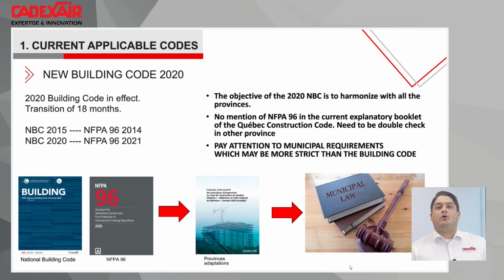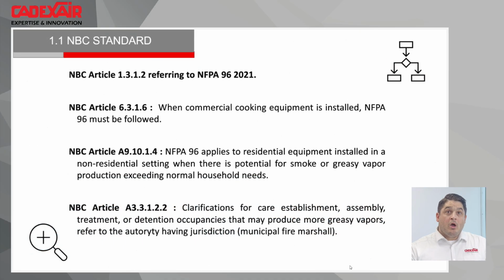And just a quick reminder, municipal law can also be applied to kitchen exhaust hood design and be more restrictive than what could happen on the provincial part. So if we are looking at the NBC, the National Building Code of Canada, and in fact, mainly all provinces use this structure. So if you go to article 1.3.1.2 in the new 2020 code, you will see this is NFPA 96/2021 that will be applied. So later on, we will tell you what has changed between the 2014 and the 2021.